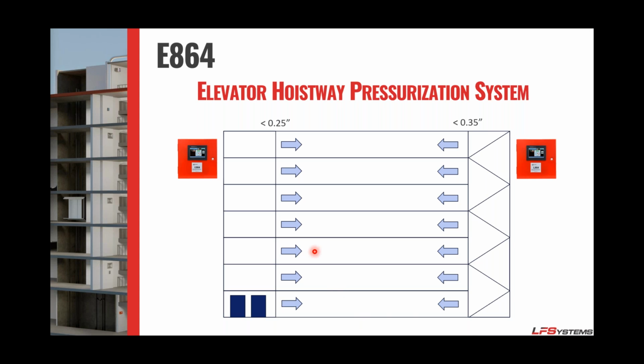If there's a blip of pressure on this floor pushing out of the elevator, the stairwell is going to say, okay, we need to put a little bit more air to make sure we don't push too hard. And we just keep going back and forth. So they're working in concert with each other to make sure that we maintain 1/10 of an inch here, 1/10 of an inch here. If we start to get to the high sides, we'll open up a relief damper. We'll make sure that we maintain it so that one is not overtaking the other.